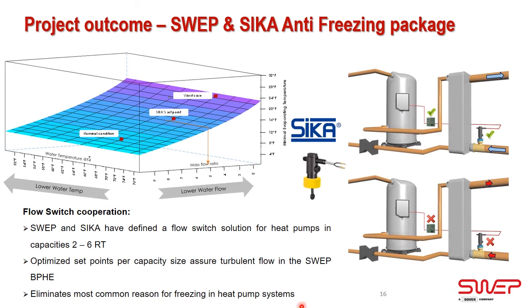Another project outcome was the cooperation between SWEP and the flow specialist company SIKA. What SWEP has seen is that the most common reason for freezing in a reversible system is that there is no water flowing on the water side. If the water is not flowing on the water side for any reason, it could be that the pump stopped working, that a valve shut, or a human mistake, and the compressor is still running, the water temperature will of course go down and freezing will happen relatively fast.